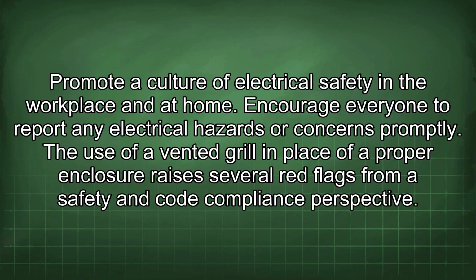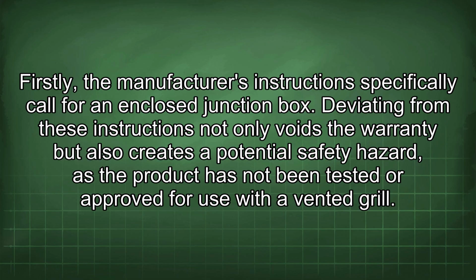The use of a vented grille in place of a proper enclosure raises several red flags from a safety and code compliance perspective. Firstly, the manufacturer's instructions specifically call for an enclosed junction box. Deviating from these instructions not only voids the warranty but also creates a potential safety hazard, as the product has not been tested or approved for use with a vented grille.